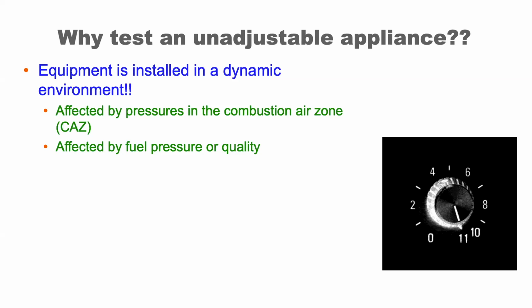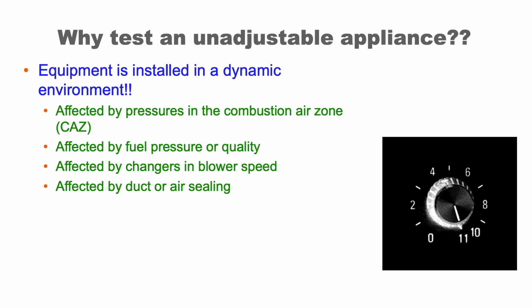It's the rate of delivery of the fuel, of the hydrocarbon to the system. It can be affected by changes in blower speed. Part of the system is designed to work at a certain rate of energy transfer, of heat transfer. If the blower, and we're talking about warm air distribution combustion, if the blower is moving at the wrong speed, too much heat can build up or too much heat can be taken away, which can change and affect the performance of the system. It can even get down to duct or air sealing. One way in terms of like a leaky return can actually pull on the combustion air zone, or in a leaky supply situation that could waste heat that goes into the wrong location in the structure.